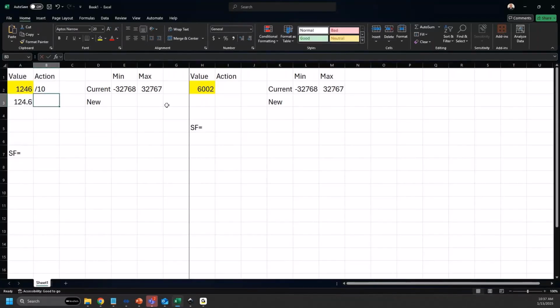Hope you're with me so far. Now, anybody who has a distribution line of 7200 volts pretty much knows by heart, for rapid recall, that the ratio of the 120 to 7200 is 60. So we're going to multiply that value by 60. Here's math I can't do in my head, but we're going to take the 124.6. That's actually not going to work. Let's multiply it just by the number 60. And we have 7476, which sounds right as a value on a 7200 volt base.